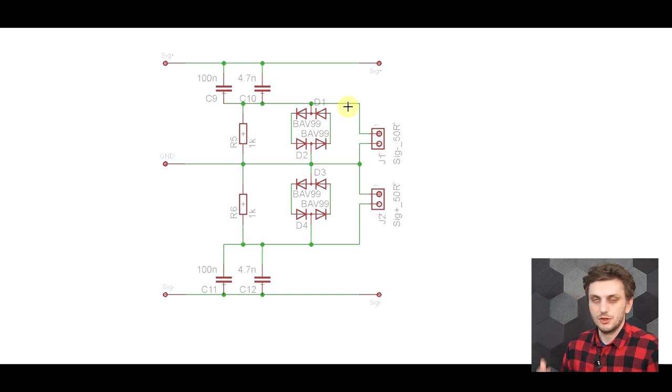And the purpose of these being for transient limitation. So you can get transients the moment when you connect the supply to your LISN or when you're connecting a very large load. Now, these transients don't really affect the LISN. That will handle them without any problems. But if you have your spectrum analyzer connected to that port, well, for the short amount of time, you can have very large voltage signals that can damage the input. And you don't want to damage your spectrum analyzer. So some form of transient limiter, maybe coupled with an attenuator, should always be used.